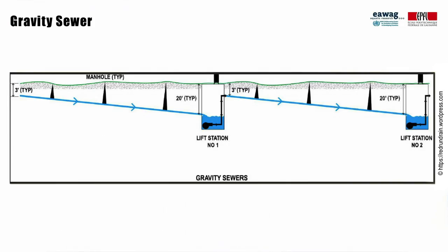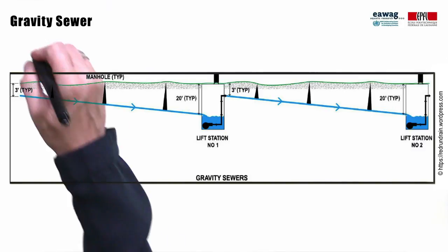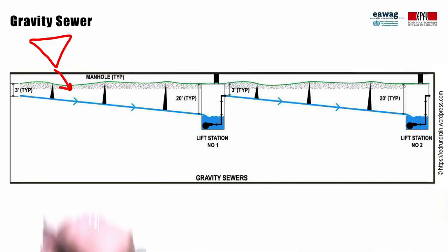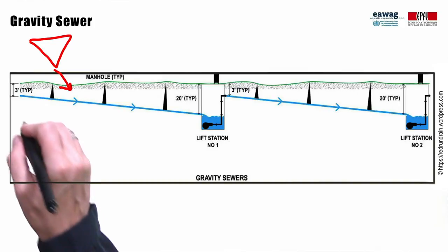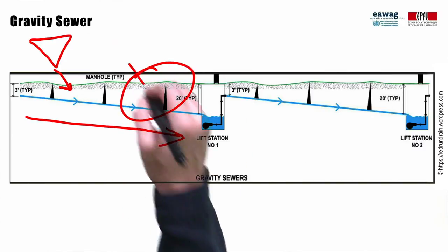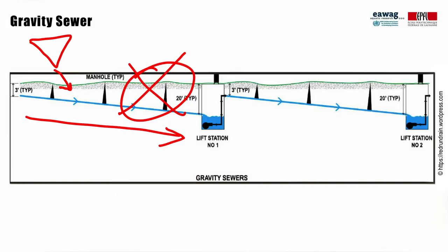Finally, one of the most important considerations when co-treating is when and how to add the fecal sludge. Fecal sludge should never be discharged to the sewer unless it has been dewatered first and the effluent is going to the sewer. Sewers are designed for the gravity flow of wastewater, and thicker fecal sludge does not have the same flow properties, resulting in blockages and overflows. To avoid shock loadings, the preferred method would be a continuous flow at a rate that is proportional to the wastewater influent.